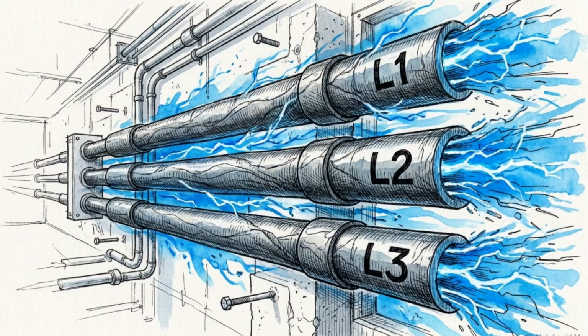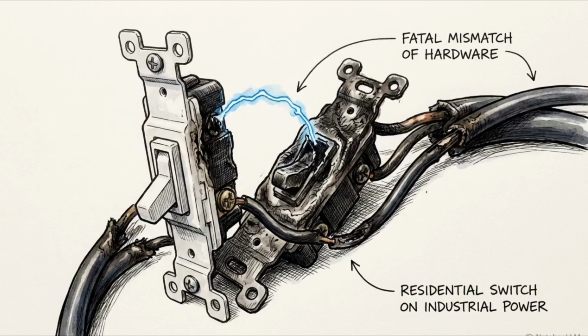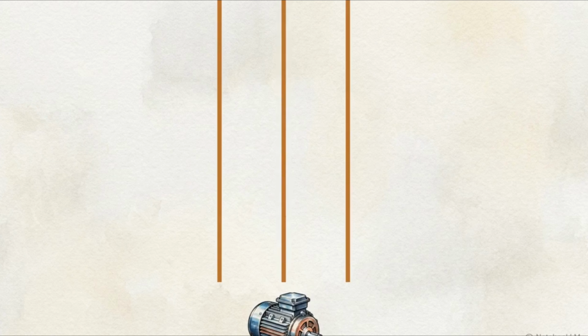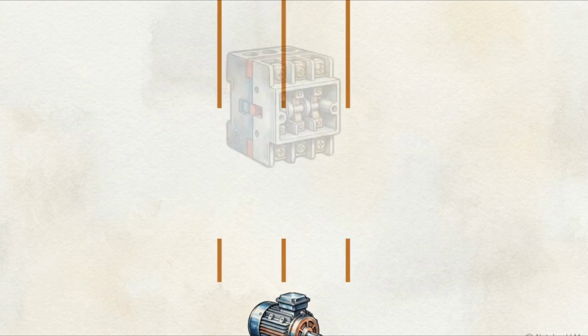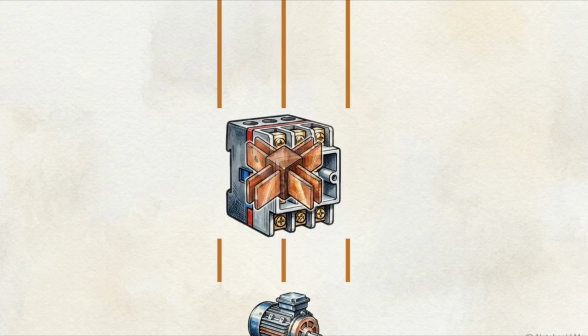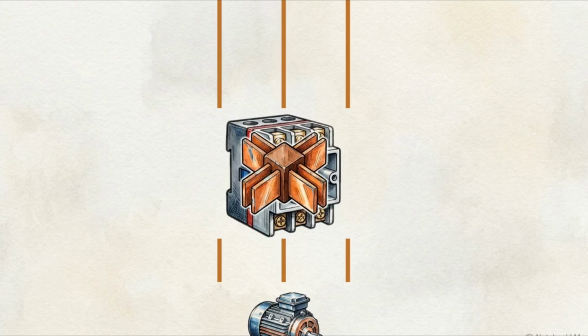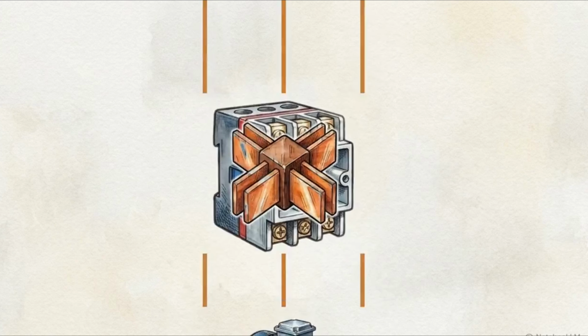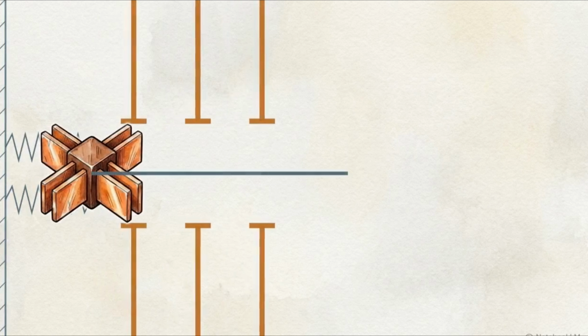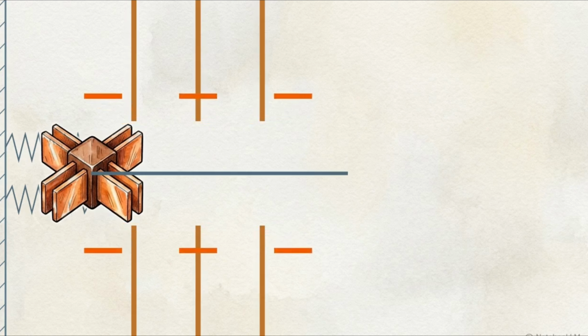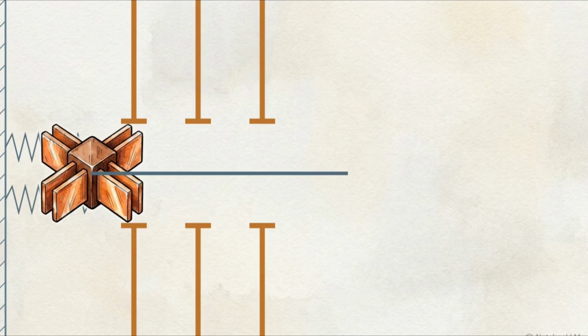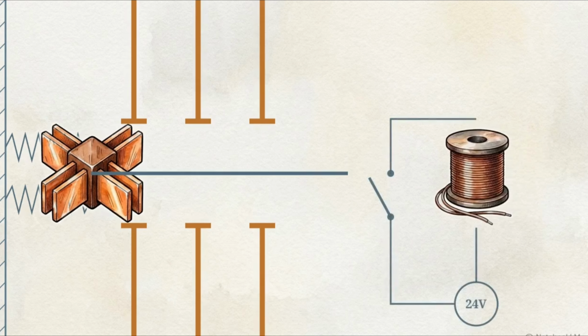Because of the massive current flowing through lines L1, L2, and L3, installing a manual light switch directly on these wires would put an operator at risk of a fatal arc flash. We avoid this danger by breaking the direct line to the motor and inserting the contactor. A contactor functions as a synchronized bridge, using a single mechanical action to close three independent high-voltage paths at once. If we look inside the contactor, we see two entirely separate systems.